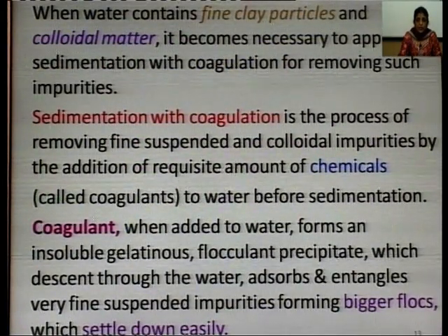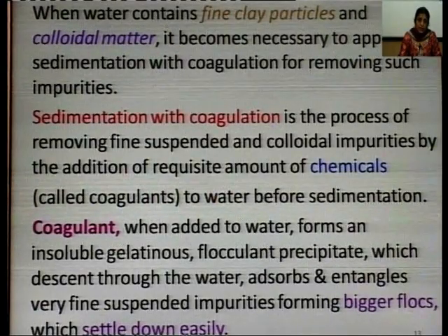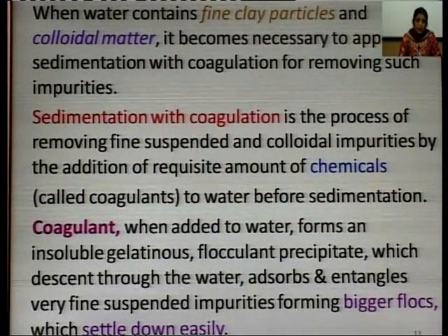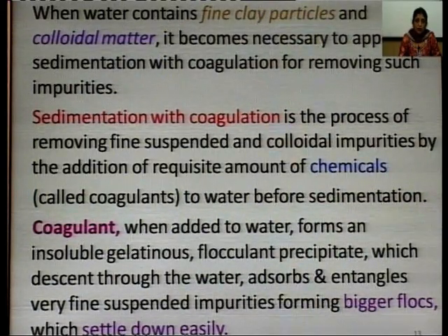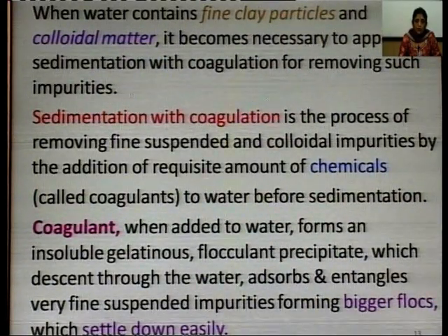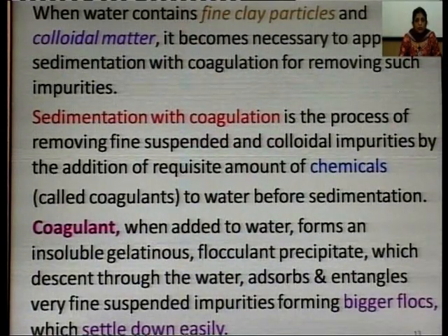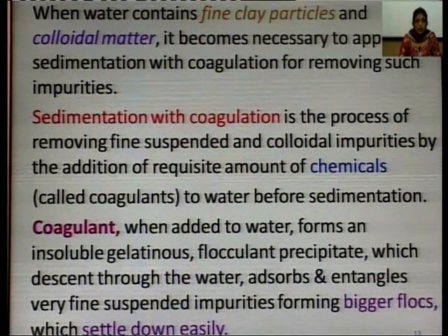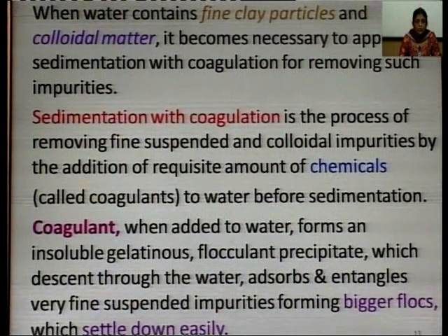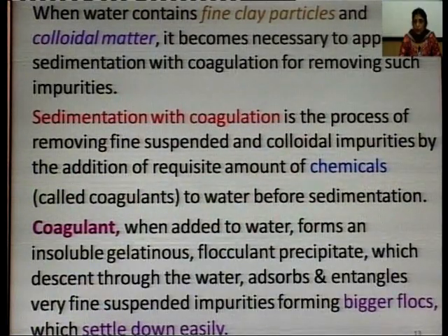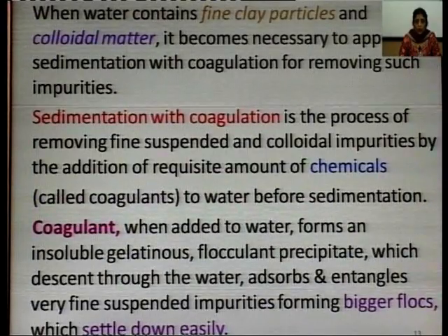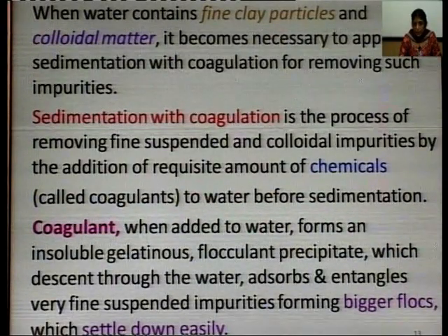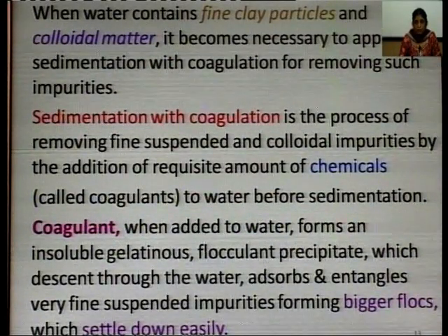So, when water contains fine clay particles and colloidal matter, it becomes necessary to apply sedimentation with coagulation for removing such impurities. Because fine clay particles and colloidal matter do not settle down immediately, or we can say they cannot be purified by sedimentation alone. So, we have to apply coagulation also. Sedimentation with coagulation, what is this process?